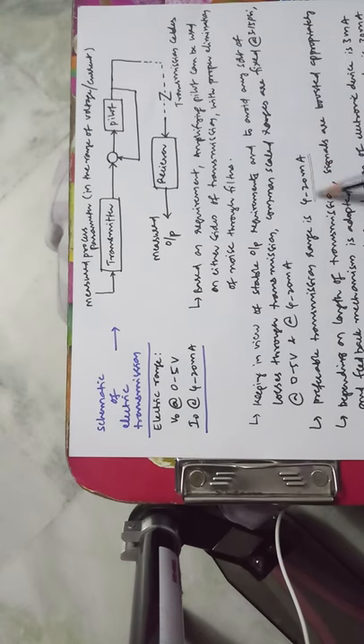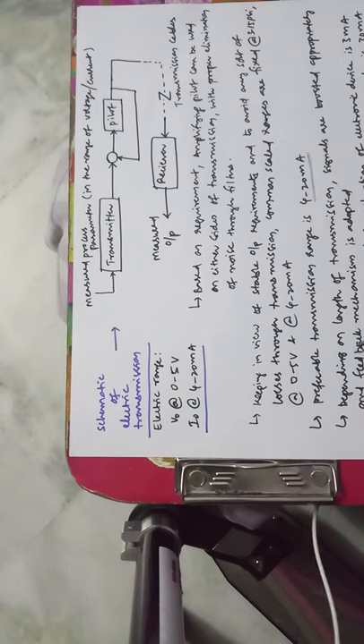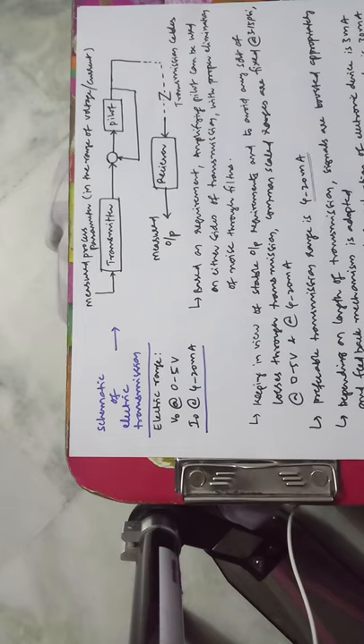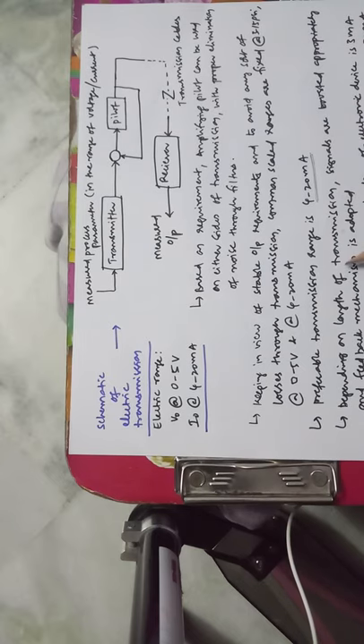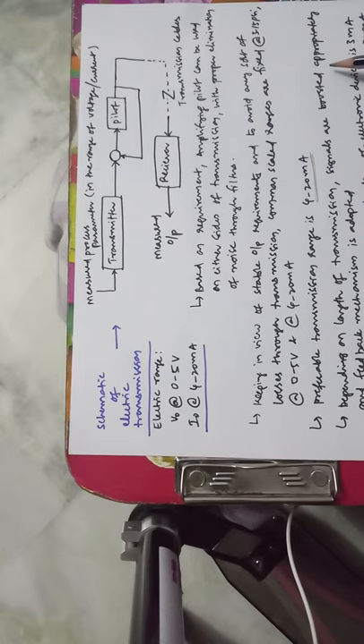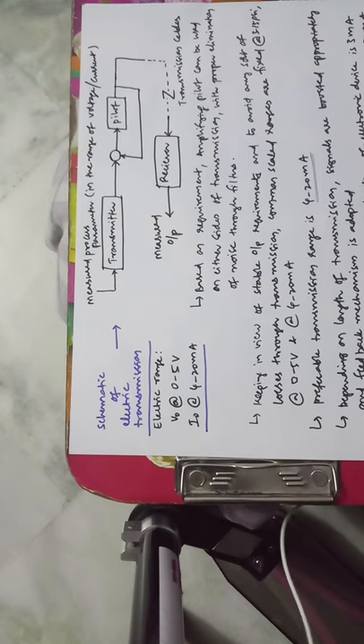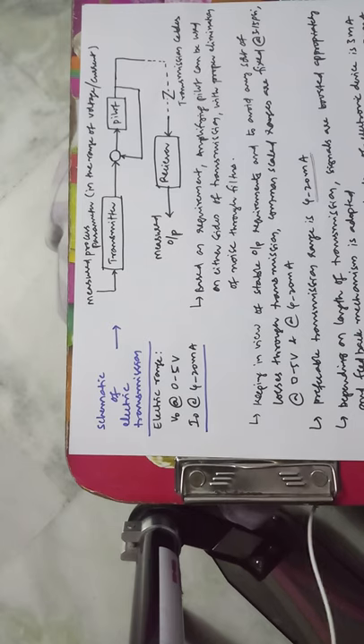The preferable transmission range in most industrial applications is 4 to 20 milliamps. Depending on the length of transmission — whether 100 meters, 1 kilometer, or 10 kilometers — signals must be boosted appropriately using amplifying pilots and a feedback mechanism must be adopted for efficient transmission.